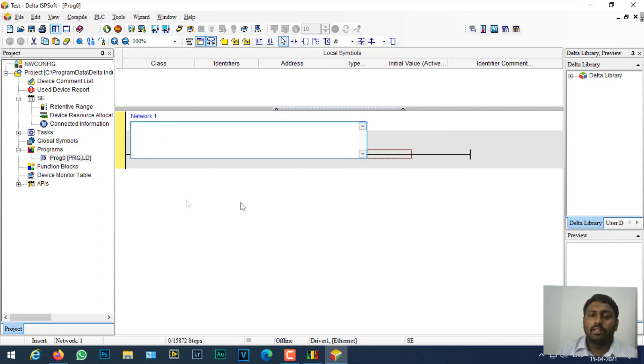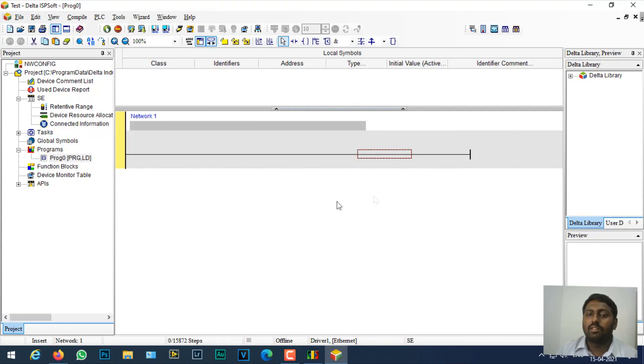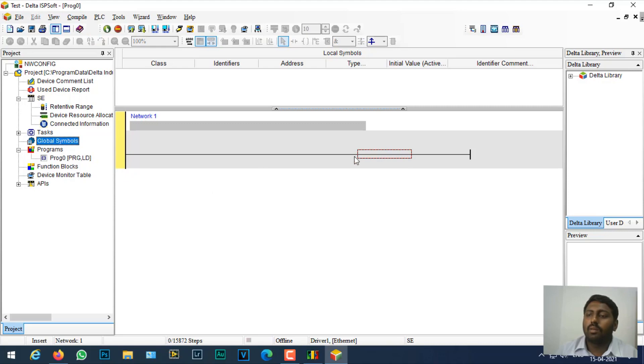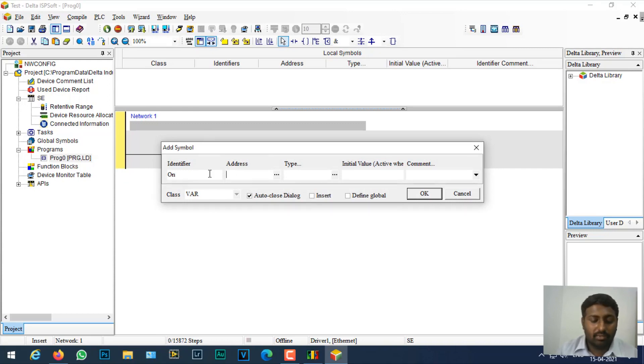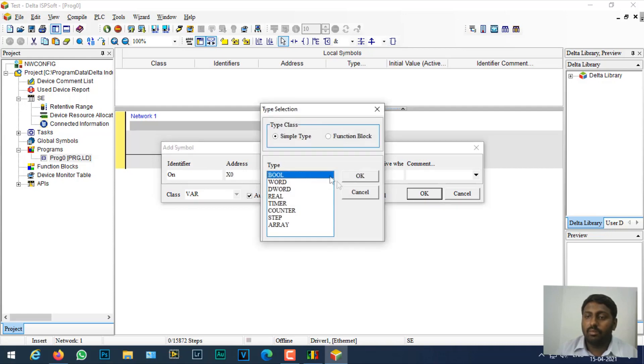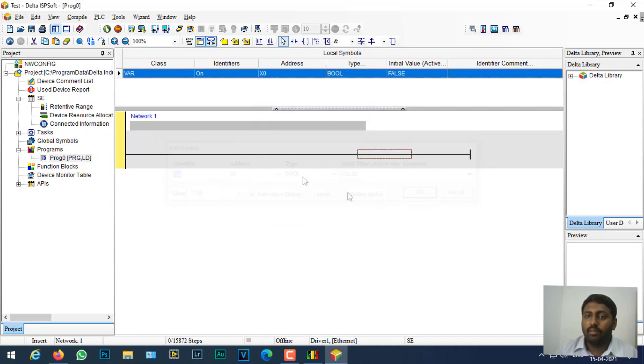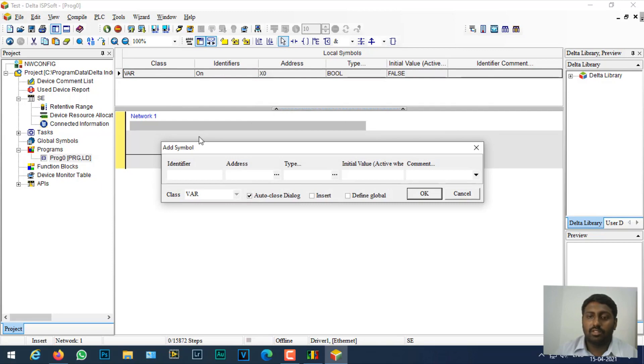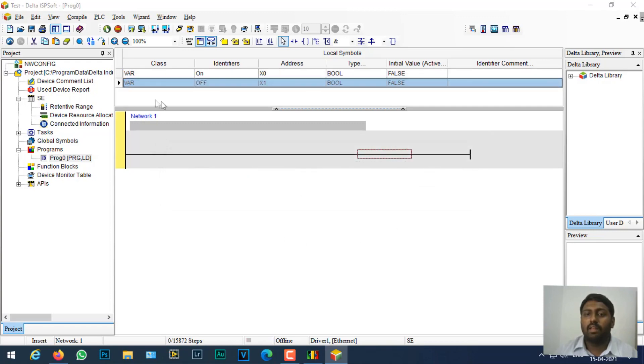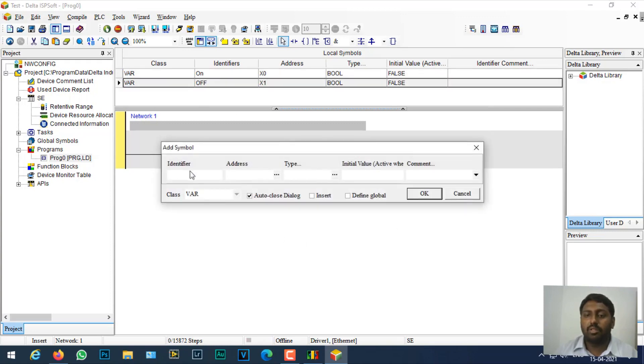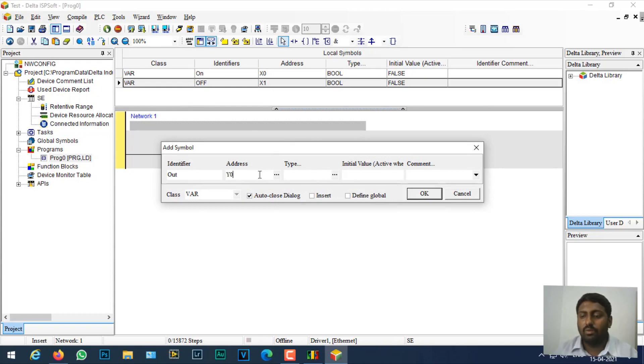The main advantage of using this programming software is that you can create tag names individually. For example, if you want to add a tag name, I'll give it as 'on' and create a device. I'll give the address as X0, type will be boolean. Again I'll give 'off' and this will be X1, type is boolean. Finally I'm going to create output and this is Y0.